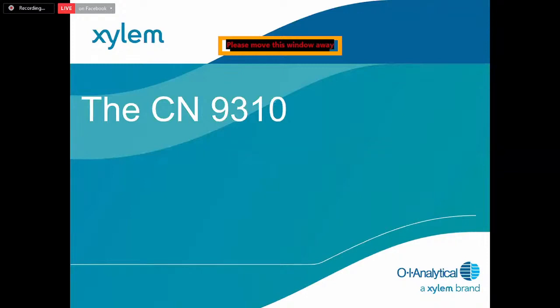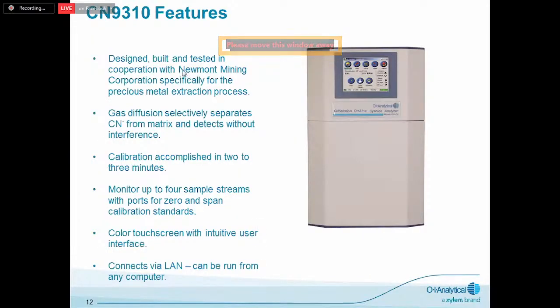And I'll start first. The previous slides gave you a background of what we're going to talk about now with the individual instrumentation. We'll start with the online instrument, which is the CN9310. This was designed and built and tested in cooperation with Newmont Mining Corporation, specifically for the precious metal extraction process. Gas diffusion selectively separates CN from matrix and detects without interference. Calibration is accomplished in 2 to 3 minutes. We can monitor up to 4 sample streams with ports for zero and span calibration standards. A color touchscreen with a very intuitive user interface is available to the operator of the instrument, and it can connect via LAN connection and be run remotely from any computer on which we have our control software installed.